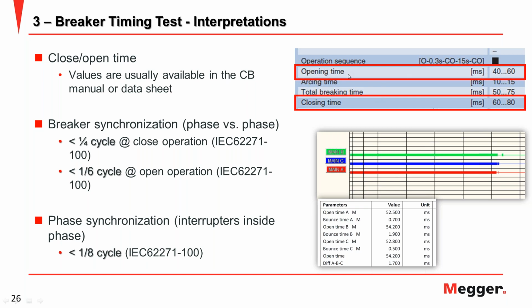They put the opening time on the datasheet. They put the opening time and closing time, with the minimum value and the maximum value. So if you know this, you can verify whether your test result is still good or needs to be investigated. If you don't have this information from the circuit breaker manufacturer, maybe you can follow this standard.